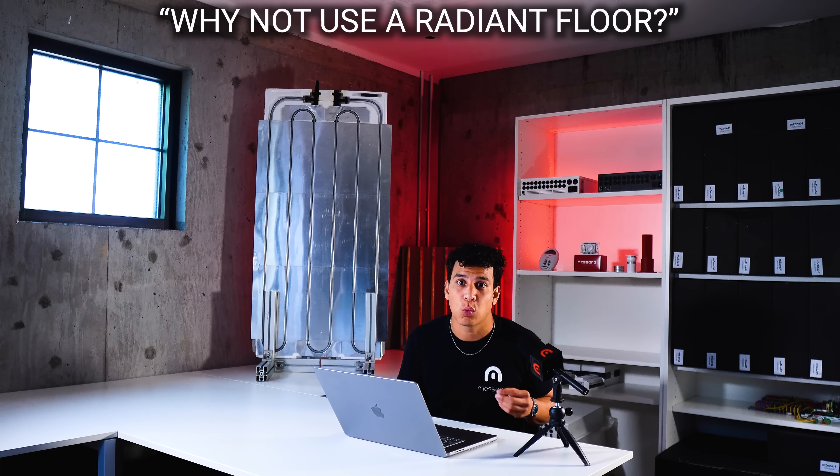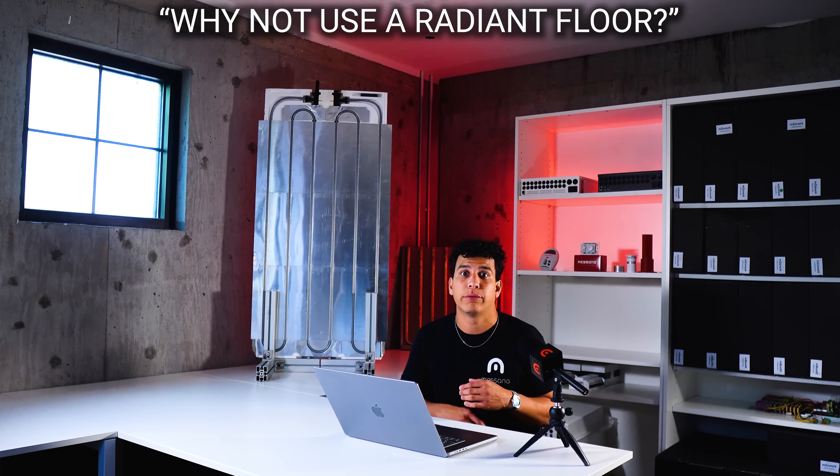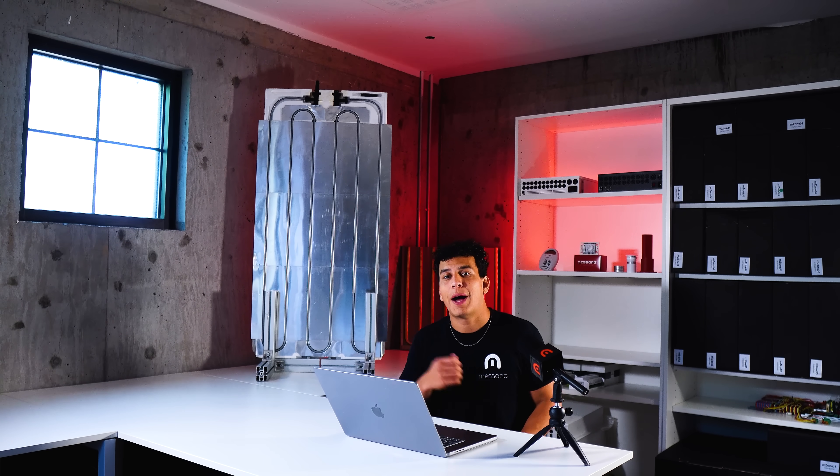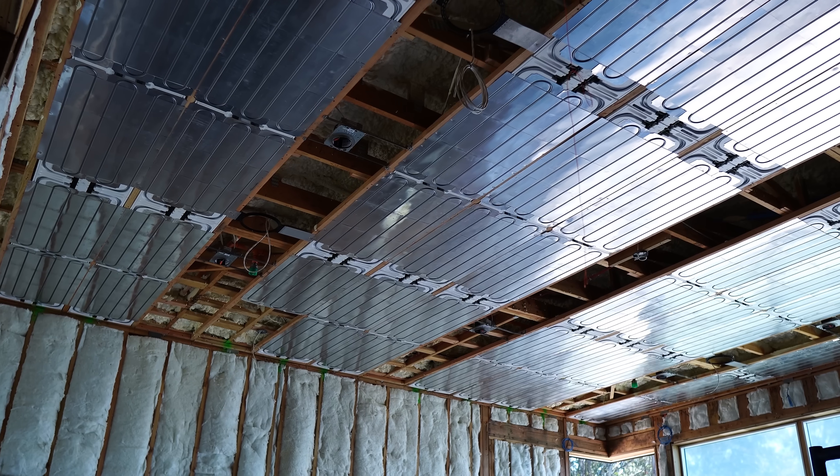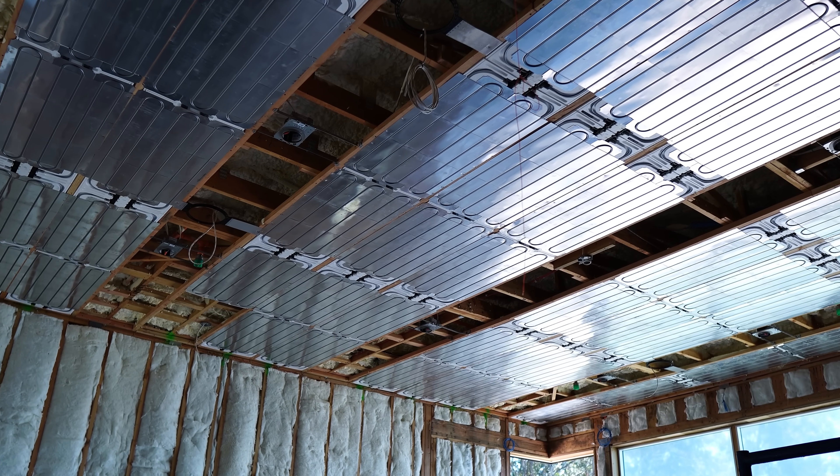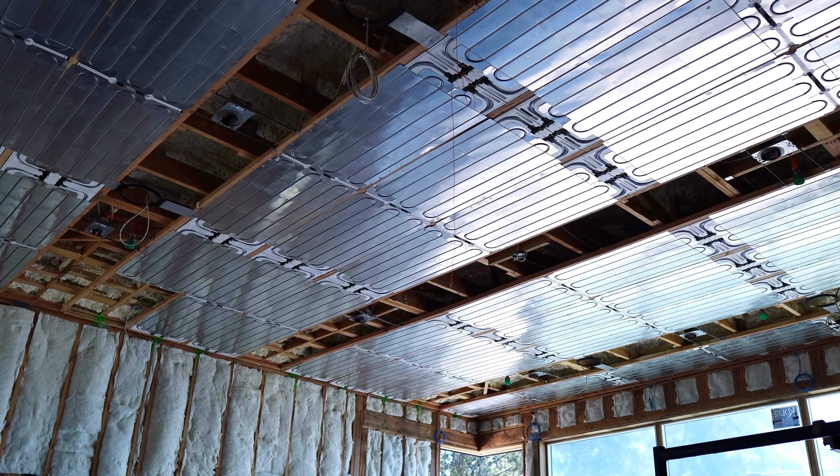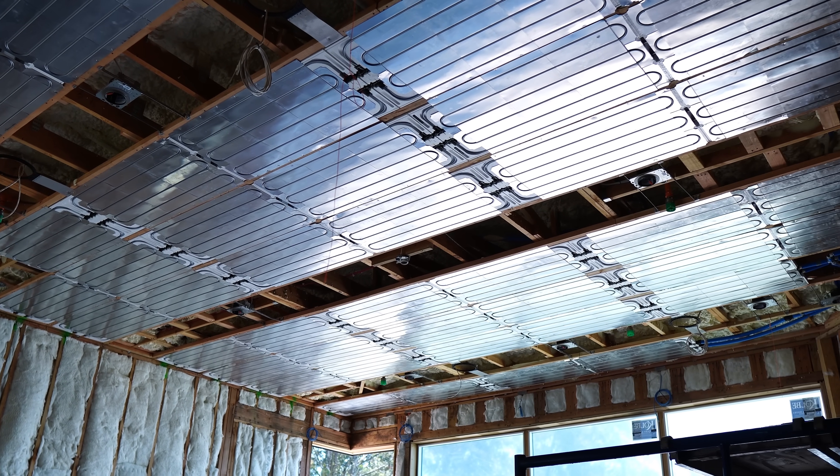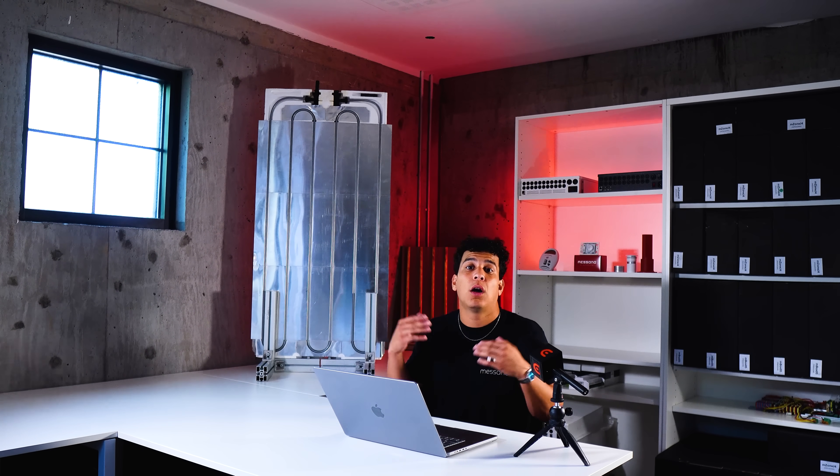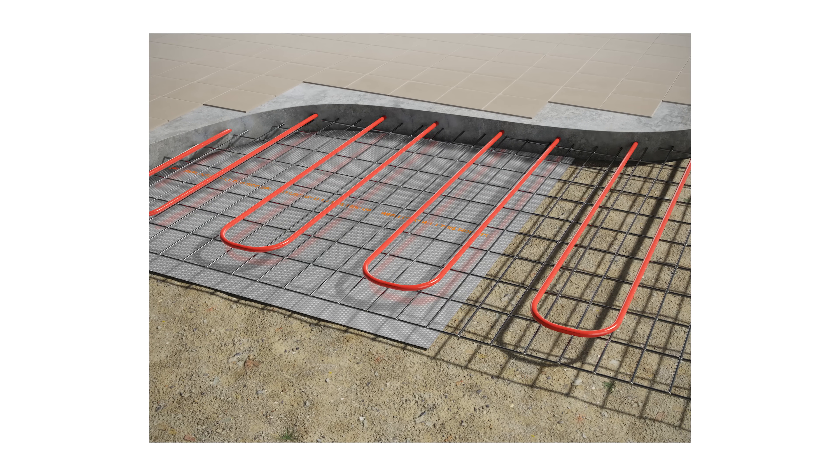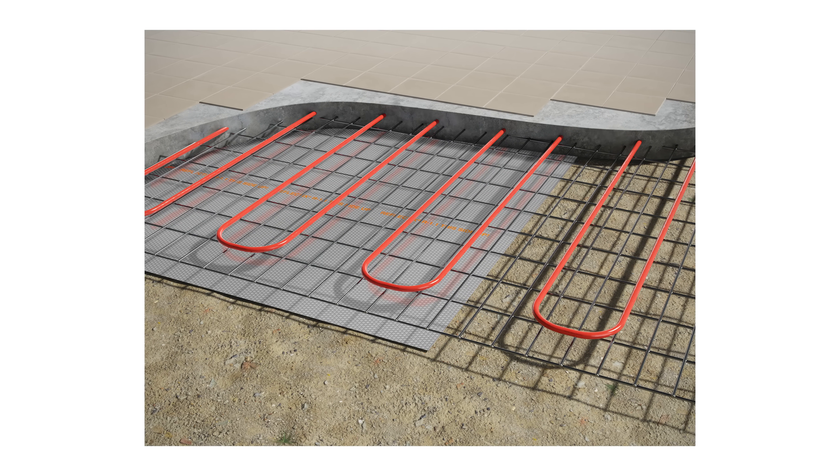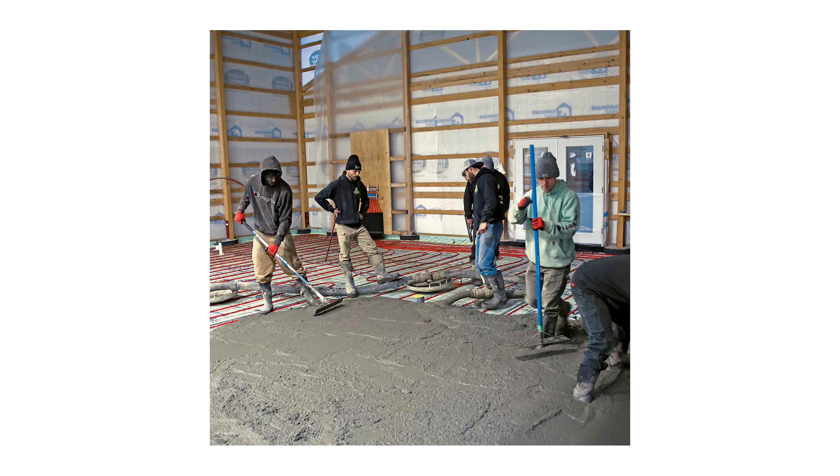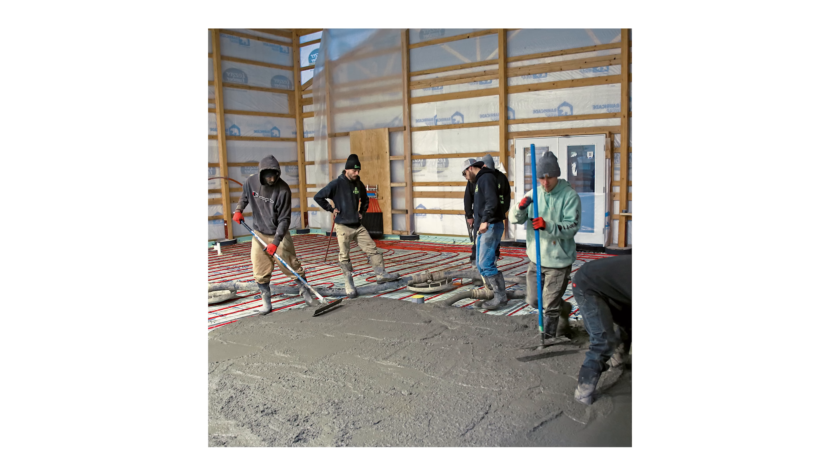Number four is, why would you not just use a radiant floor? Radiant floors are already pretty popular, so why move that technology to the ceiling? We moved our radiant surface to the ceiling to achieve a really low thermal mass so our panel can respond very quickly to changes in humidity. When providing radiant cooling, we want to avoid condensation, so we need a really fast responding panel. If there's a sudden change in humidity, we can change the temperature of the ceiling panel much faster than traditional poured concrete slab radiant floors. Those are very high mass systems and slow to respond.